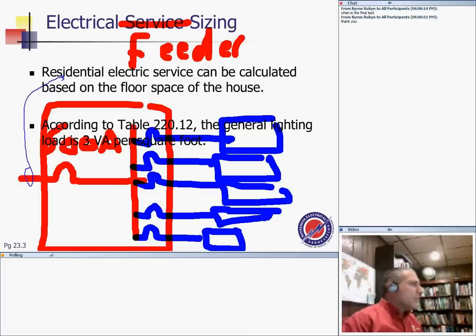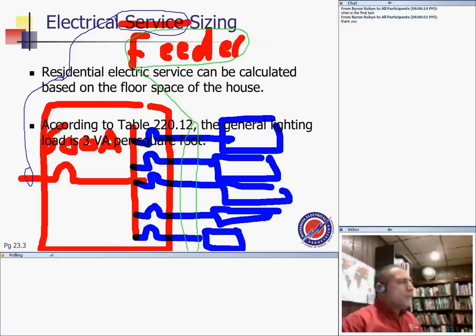Go all the way and circle the word service. That's power coming to your building. And everything else, as we all know, all these cables here going to different apartments, these are going to be your feeders. Now, Gerald, my friend, if you're doing a house, 100 amp panel or 200 amp house, you only have service. You don't have feeders unless you have a sub panel in your garage or your shed, a 60 amp sub panel or 100 amp sub panel. That would be a feeder.